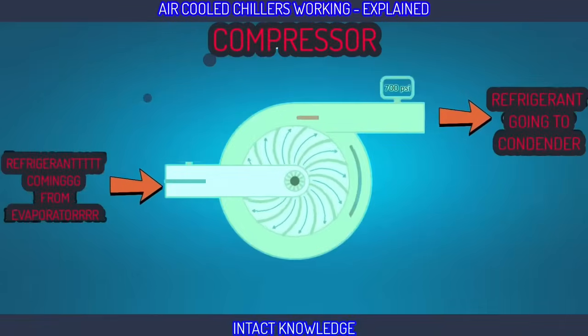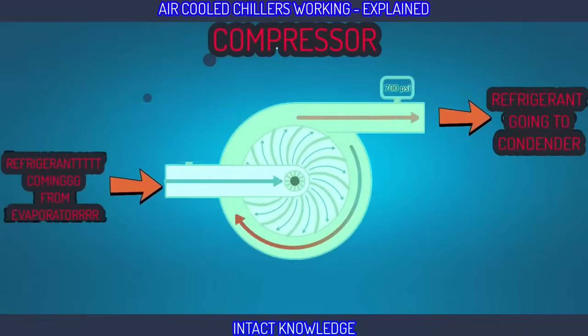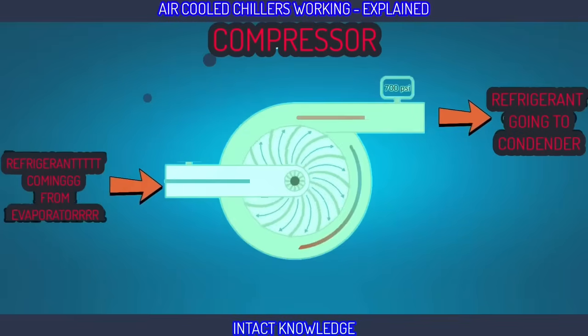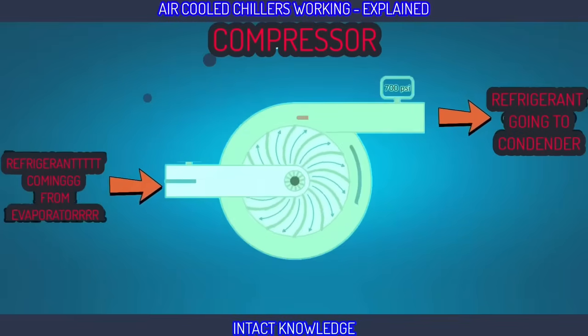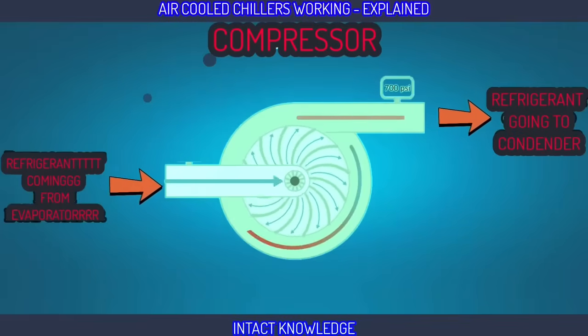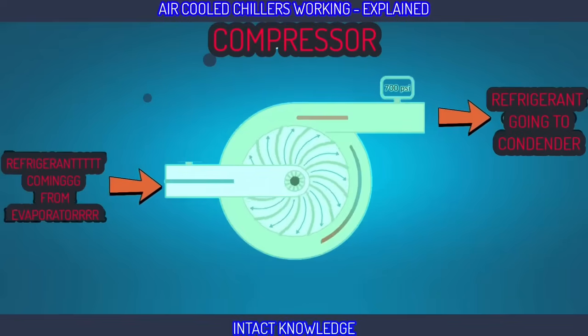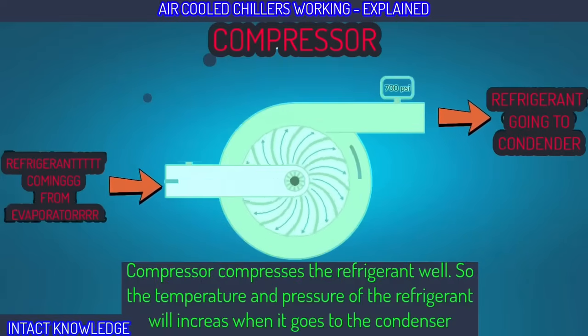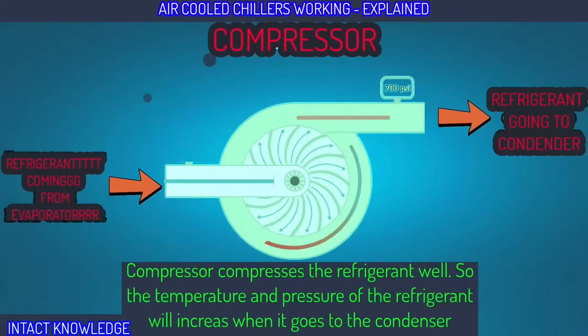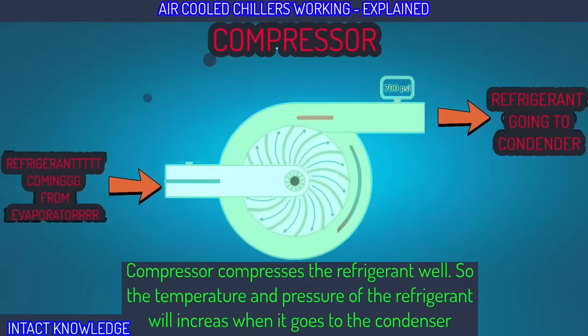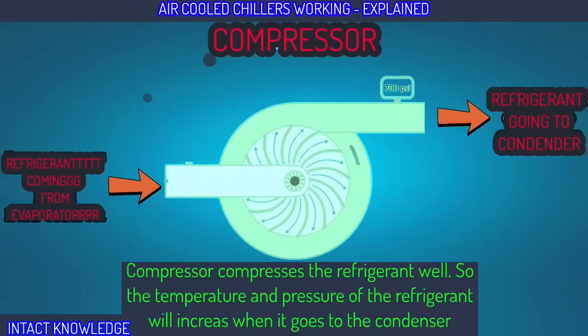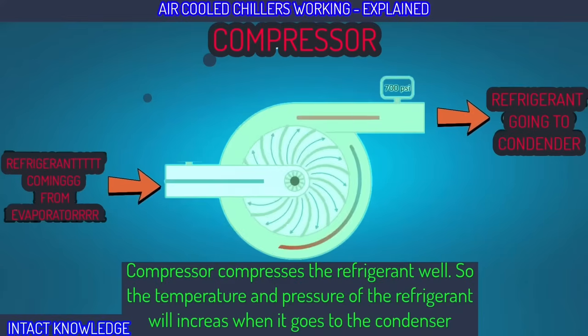Now let's see what compressor does. After the refrigerant turns into a vapor inside the evaporator, the compressor sends all that vapor to the condenser. The compressor compresses the refrigerant well while sending it to the condenser. Due to this, the temperature and pressure of the refrigerant will become very high.